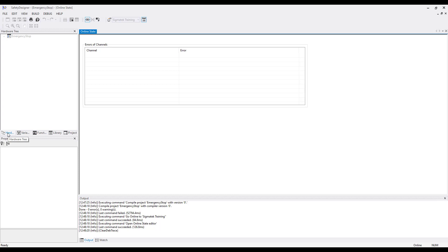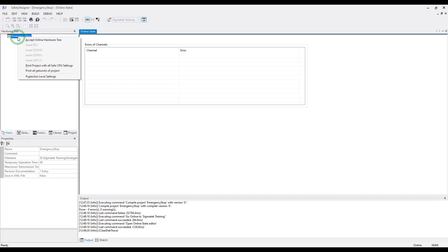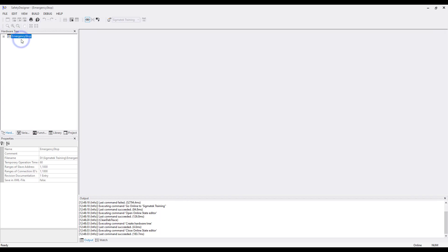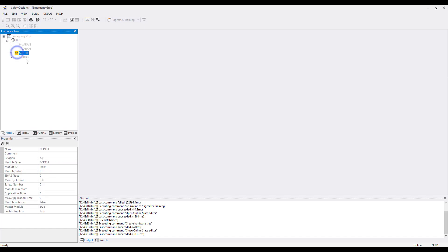Now you are online and able to upload the hardware. Go to the hardware tree, right-click on Emergency Stop and choose Accept Online Hardware Tree. The hardware is uploaded. Open the project name with the plus. Inside there is the PLC. Open this with the plus and there is the safe CPU. Next to the safe CPU you can see all the different safety modules.